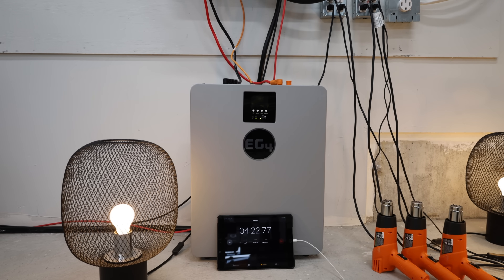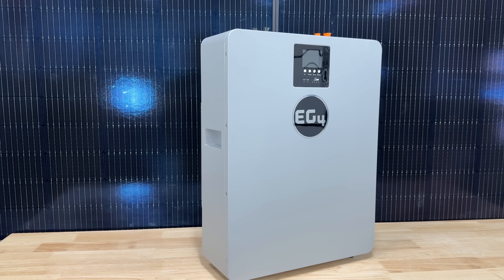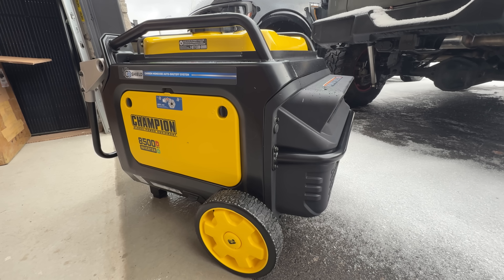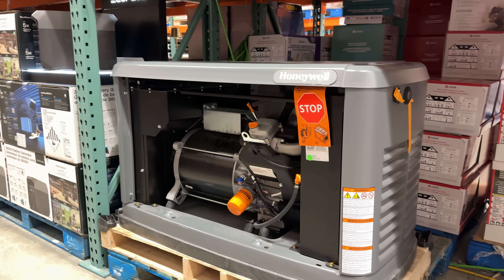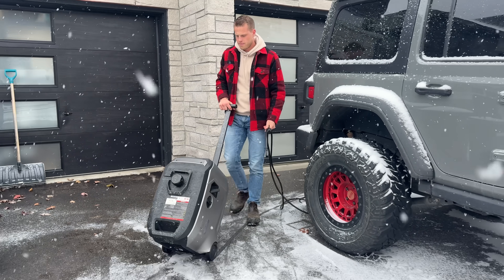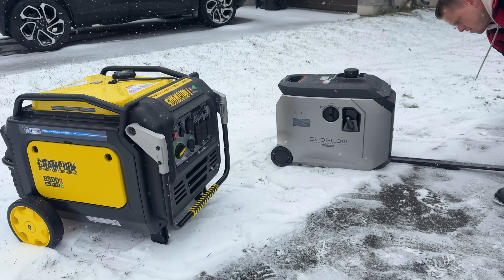If you're trying to run essentials at 20 kilowatt hours with those indoor 100 amp hour wall mount batteries, something like a 6,500 watt Champion generator running for three hours would charge all of those batteries from zero to full. Of course, you can get bigger generators that run less, or smaller systems that don't need as much power to charge — which is kind of what I do. I have a small system and only need to run the generator for about an hour a day to keep it charged up. Maybe two hours if I forgot I was only supposed to be using essentials and went absolutely ham cooking a turkey dinner.